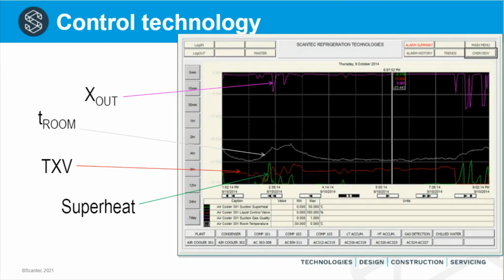So this screenshot here is from a SCADA system of a plant that was installed approximately 5 years ago. What is important and interesting here is when we compare the superheat signal with the quality signal leaving the evaporator. The superheat signal you can see down the bottom there, the green signal, and the quality signal is the top signal called X out. You can see we can have wet suction at the same time as we have positive superheat. This is a peculiarity we observe in almost all the systems that have been installed.